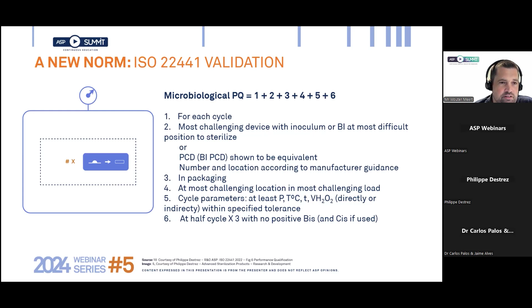For example, do you use sterilization wraps, or do you use Tyvek? Do you maybe do double packaging of Tyvek? That means you need to declare yourself in which type of packaging you say, this is how I want to validate my devices. And of course, if you look at the cycle parameters, you now have the variables you need to look at with a specified tolerance. And like Philippe told, it's the half cycle with no positive BIs that will at the end declare that your validation is in order. Next slide.